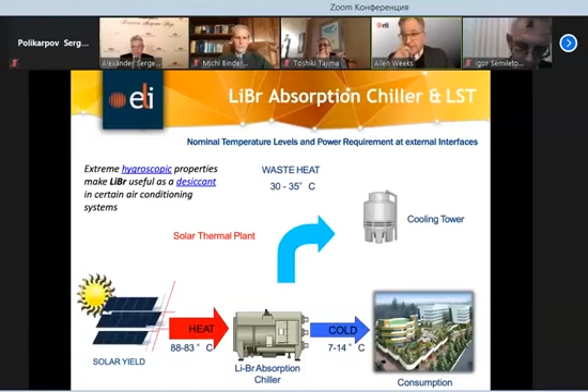Basically, these are lithium bromide systems, which is a very important desiccant, and we use thermal collectors to collect heat up to 88 degrees. Based on that, our chillers can cool it down to as much as 7 degrees Celsius. This not only takes away the heat, but also takes away a good bit of the humidity, which is important for us.